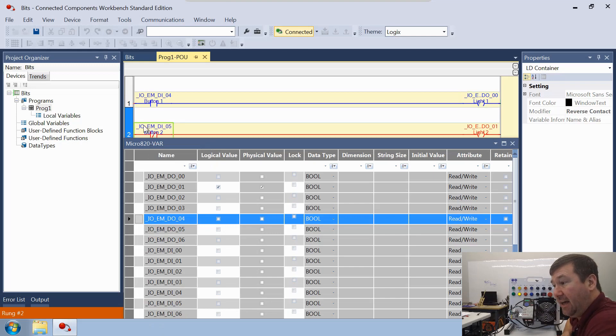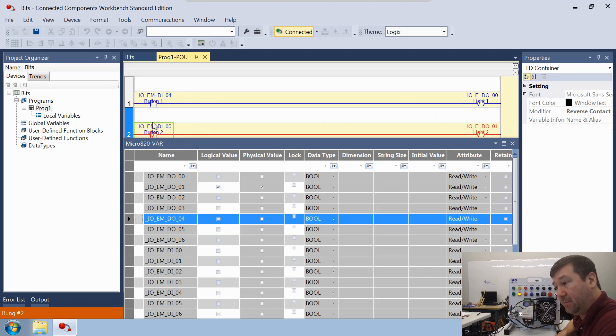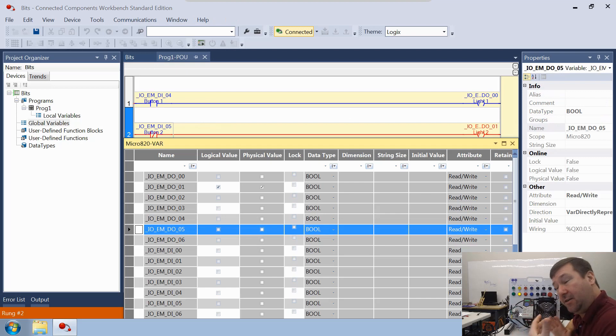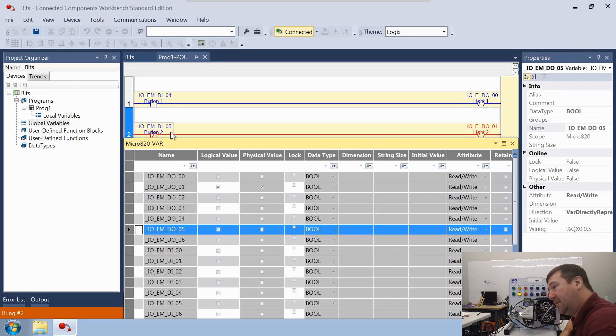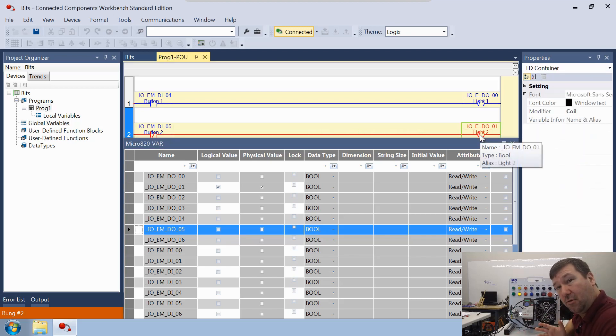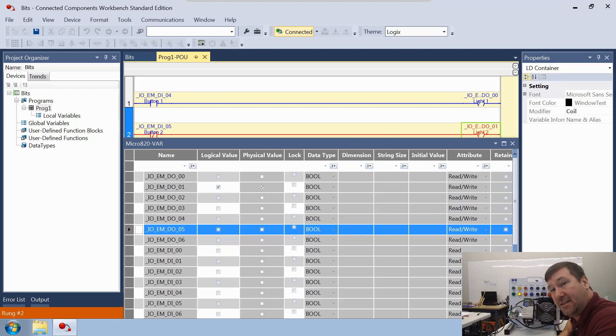Now let's look at this instruction. It's called a Reverse Contact. A reverse contact goes and looks for a 0. Where? At Input 5. Do we have a 0 or is the box unchecked? Yes — so this instruction is true, because it was looking for a 0 and it found one. That's what the red indicates — a true condition — and it's passing true conditions on to this coil. What does a true coil do? It writes a 1. Where? To Output 1. And that's why you're seeing the checkbox there.